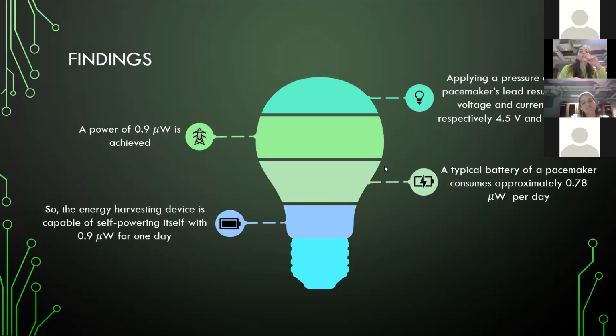Now, the findings of this research are the following. Applying pressure on the pacemaker's lead results in a power of approximately 0.9 microwatt, with a voltage and current of 4.5 volts and 200 nanoamperes respectively. And as we know, a typical pacemaker consumes around 0.78 microwatt per day. So we can conclude that the energy harvesting device is capable of self-powering itself with 0.9 microwatt for 1 day.